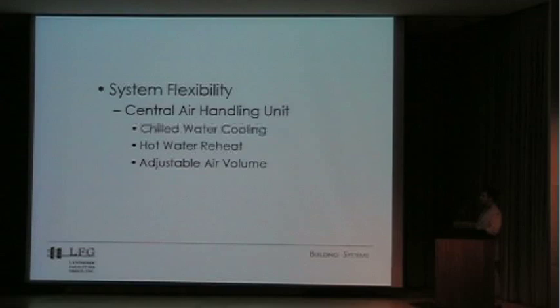There's a hot water reheat system incorporated, which allows us to do dehumidification for a museum environment if the client so chooses in the future. And there's chilled water cooling, where we're converting geothermal energy into chilled water and using that to get extra cold air, allowing us to do all of these functions at the same time.